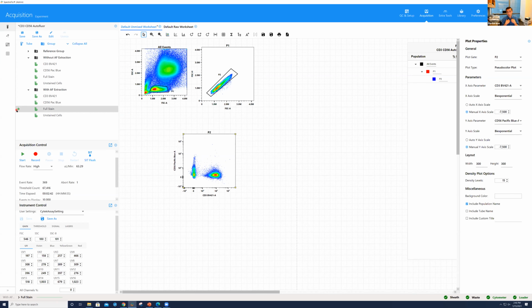So here's my take. I think that without autofluorescence extraction, if you have 10 colors, it's just using the 10 signatures to do the unmixing. And so every abundance that it's calculating of those 10 fluorochromes will include the abundance of that fluorochrome plus autofluorescence. If you click the box autofluorescence extraction, it unmixes with the 10 signatures plus the autofluorescence signature. And so it calculates directly the amount of autofluorescence, meaning that all the other 10 fluorochromes will not have any autofluorescence signal added to it. So I think that's an important distinction. It's not subtracting autofluorescence from anything.